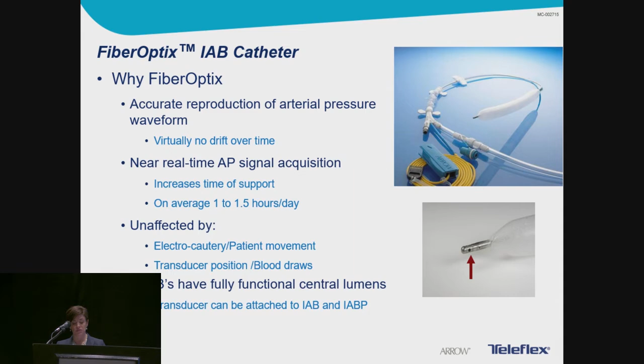Now, in addition, the sensor is unaffected by electrocautery, patient movement, tubing length, air bubbles, all those normal things we're used to. And fiber optic balloons from Arrow do have a fully functioning central lumen for monitoring the AP source from the same location as the FOS sensor. This can be used to verify accuracy.